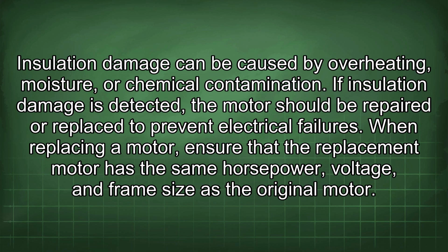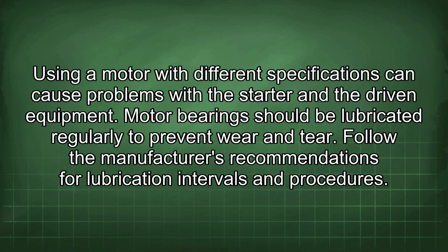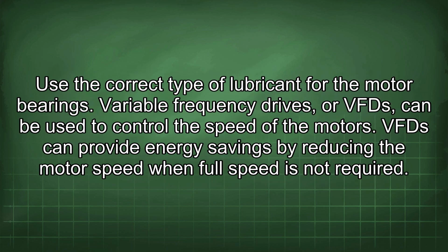When replacing a motor, ensure that the replacement motor has the same horsepower, voltage, and frame size as the original motor. Using a motor with different specifications can cause problems with the starter and the driven equipment. Motor bearings should be lubricated regularly to prevent wear and tear. Follow the manufacturer's recommendations for lubrication intervals and procedures. Use the correct type of lubricant for the motor bearings.